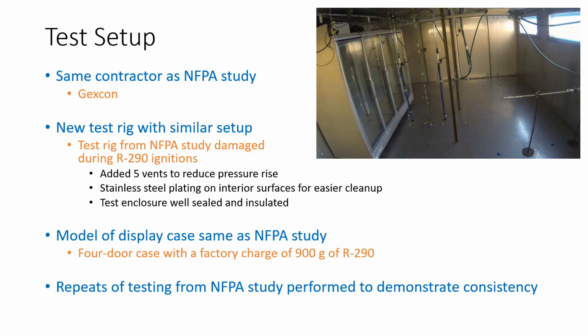This was a four-door case that came with a factory charge of 900 grams of propane. Several dispersion and ignition tests were repeated with propane to confirm consistency with the previous NFPA study. What we found was excellent agreement in the results between these two studies. Next slide, please.